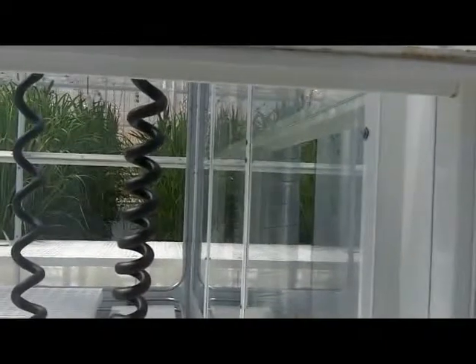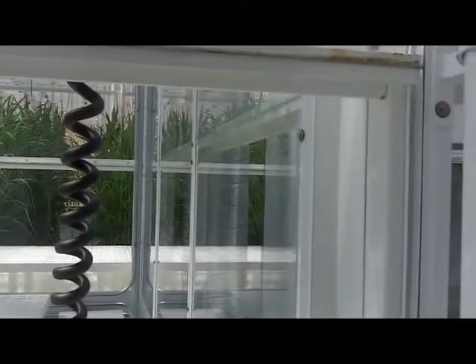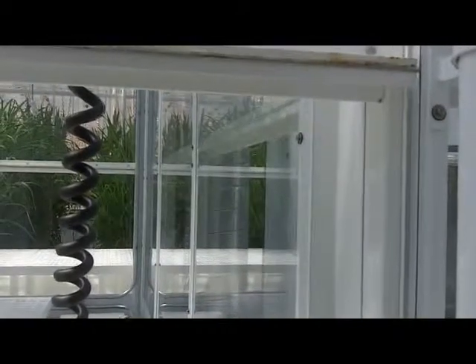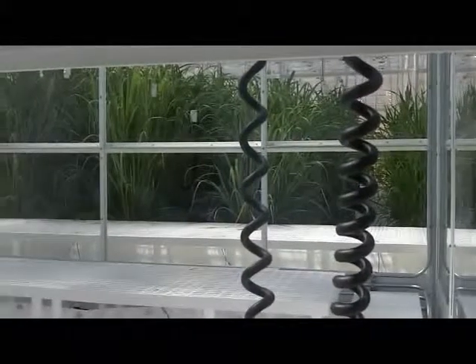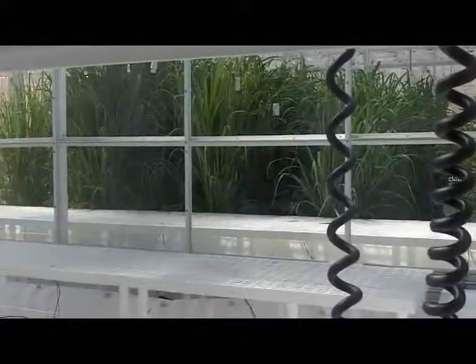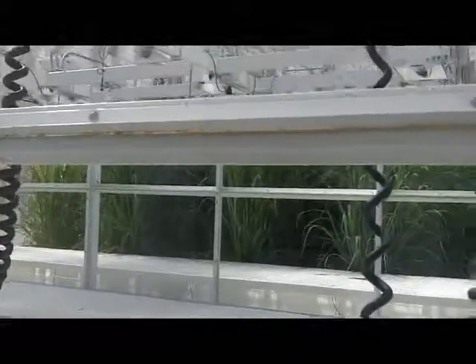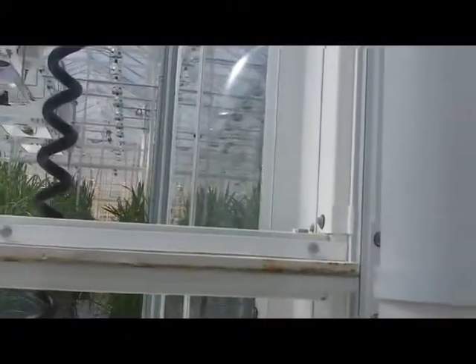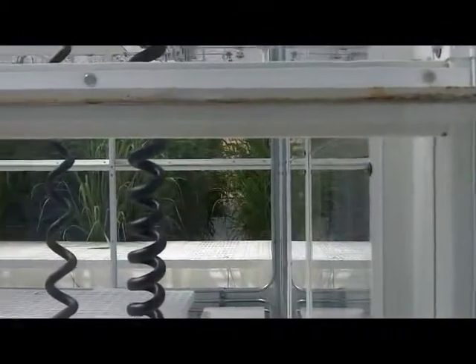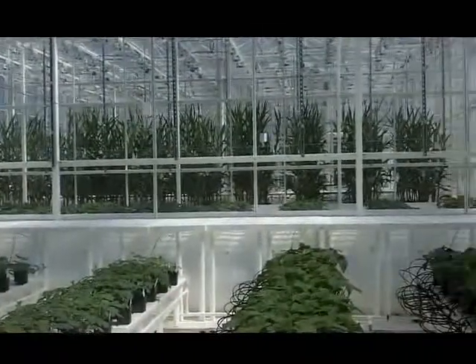As you pointed out, it is a one-of-a-kind facility. There's nothing like it anywhere else in the world. So it's not necessarily the individual components that comprise this facility. It's bringing together all of the components in a way that no one else has. From the haze glass that allows more light to come in and get evenly diffused around the facility so that we maximize the amount of light, to 100% air conditioning, which virtually no one else does. Everyone else is using evaporative cooling, which is mostly good until your relative humidity climbs to a point at which you can no longer cool the facility.